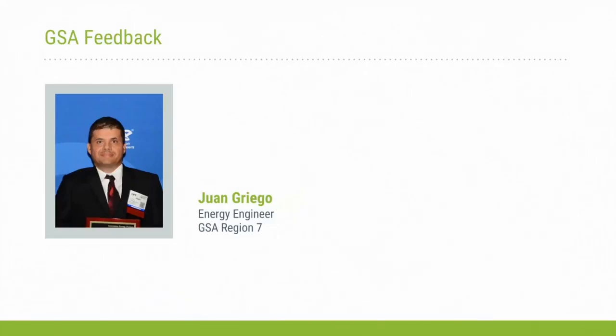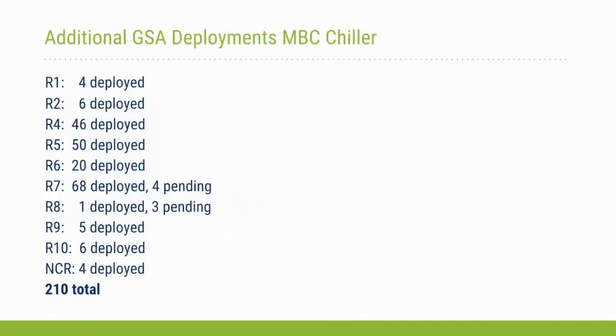Good morning, everyone. It's an honor for me to be here and talking about our experiences with the deployment and operations of these mag-bearing chillers. Next slide. Since the release of the GPG report on the mag-bearing chiller technology, GSA has seen an uptick in the deployment of the mag-bearing chiller technology. Overall, GSA has deployed 210 of these mag-bearing chillers. Region 7, as a region, we have installed 68 of them with 4 pending. Next slide.